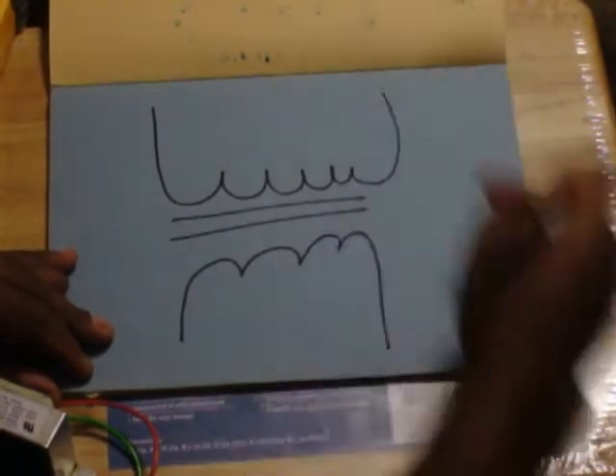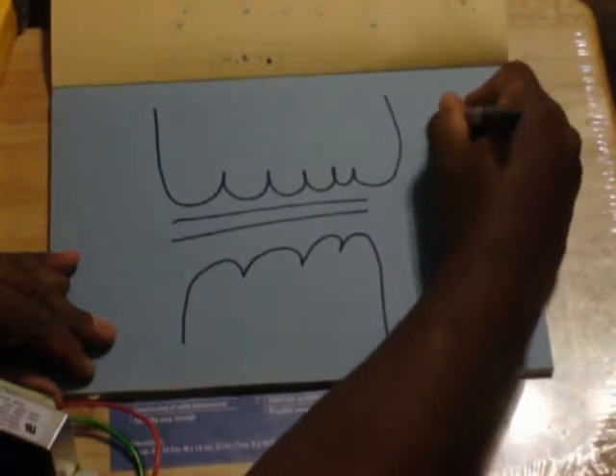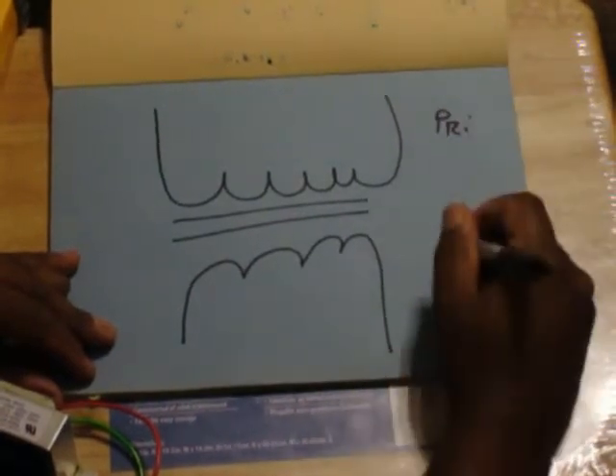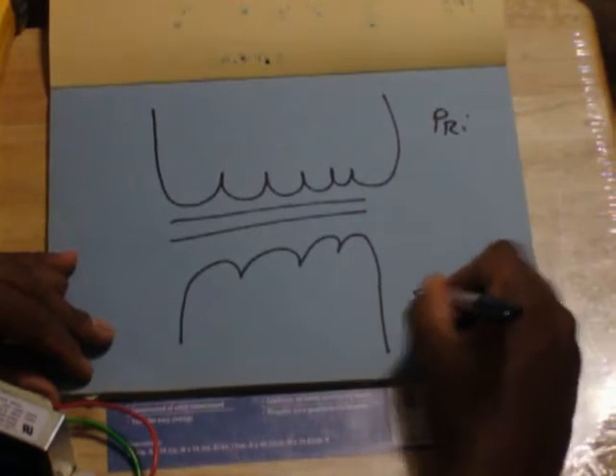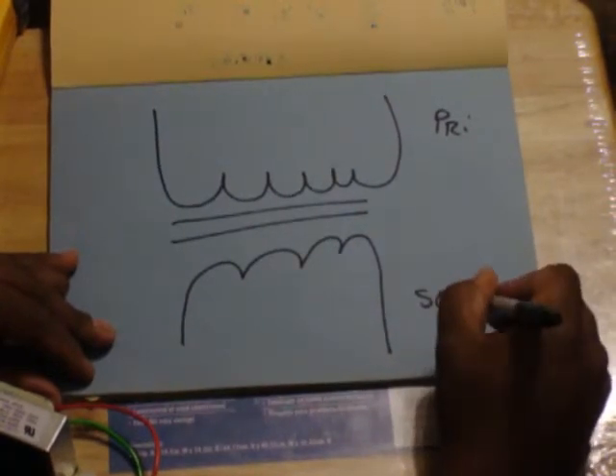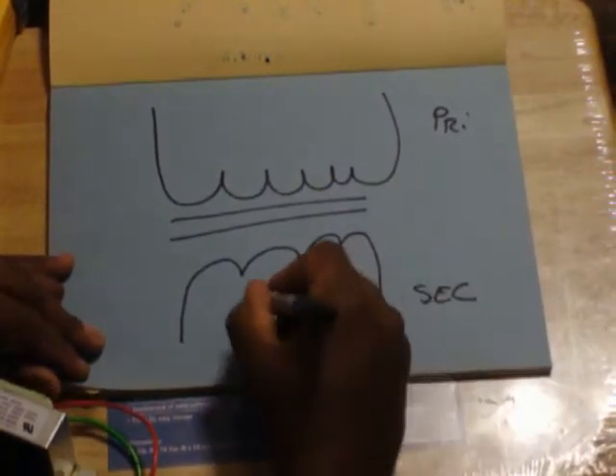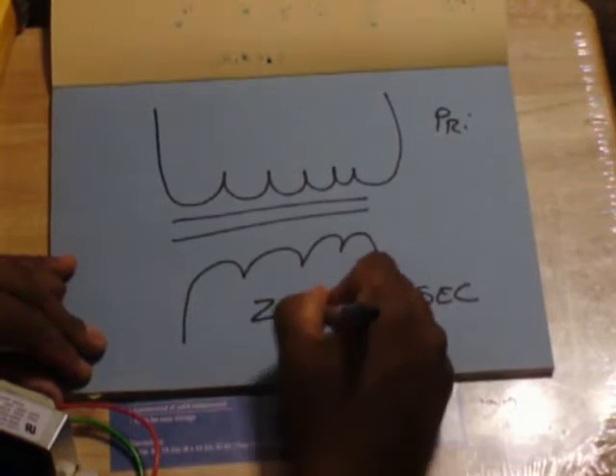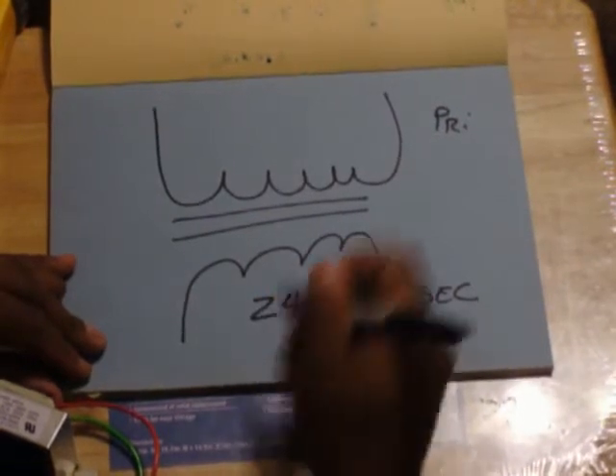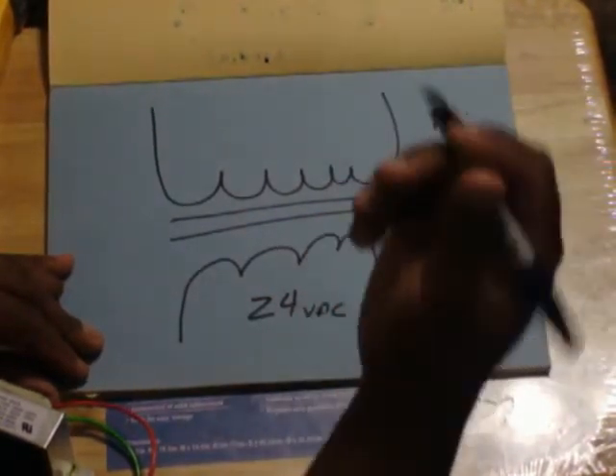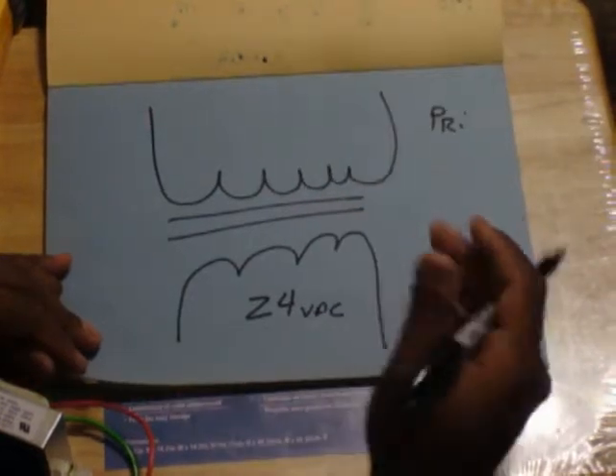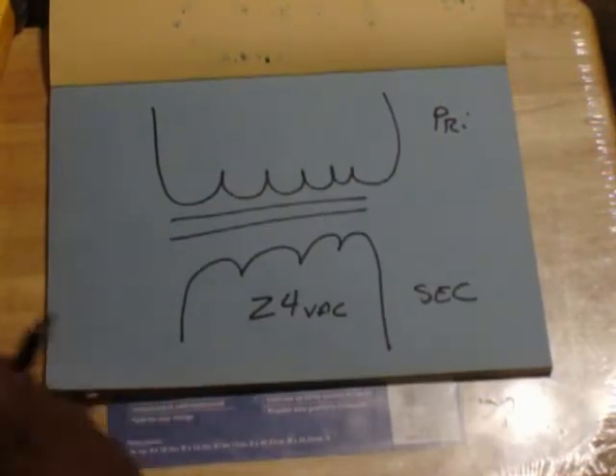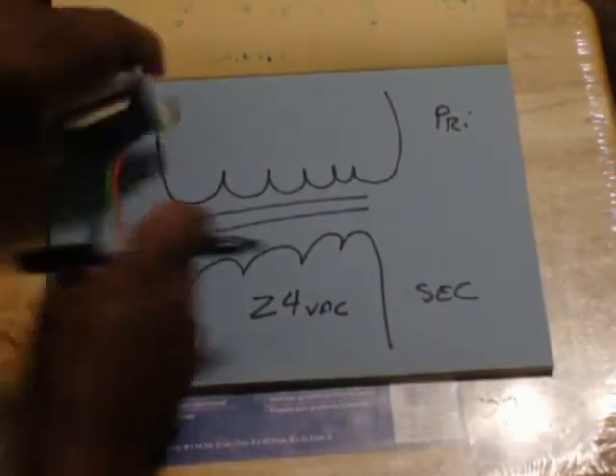The set of windings that you apply power to is called your primary. You're going to get a voltage out of your secondary. For air conditioning, your secondary voltage is 24 volts AC. Now in your primary, you could apply 110 volts, 120, 208, 230 volts, but make sure you have the right transformer. But what we're going to talk about here is what we call a multi-tap transformer.